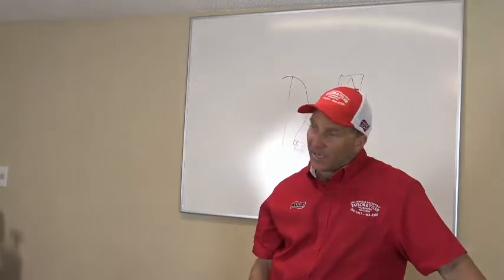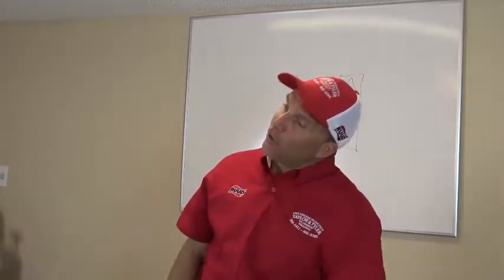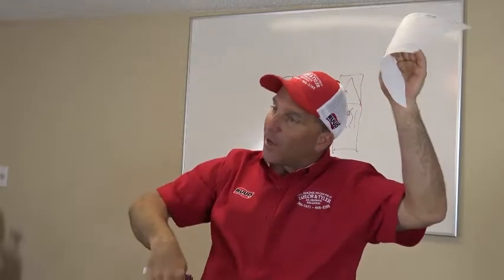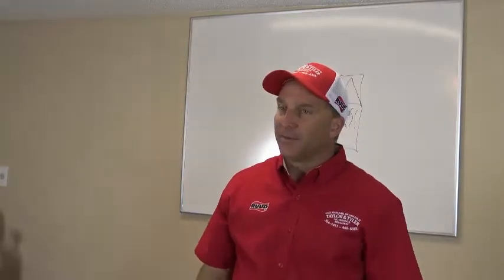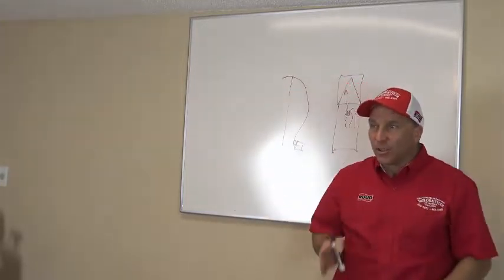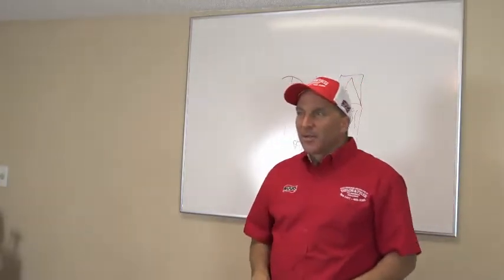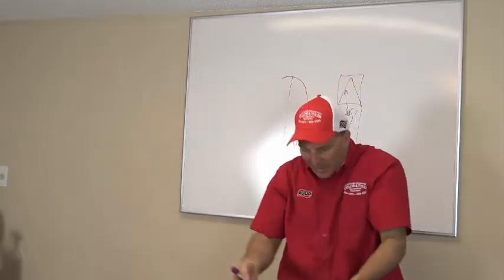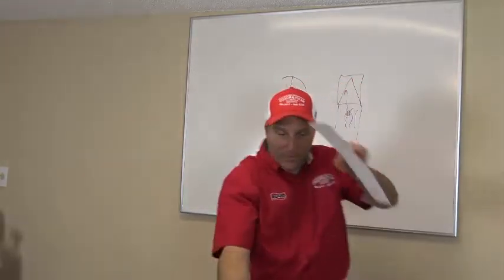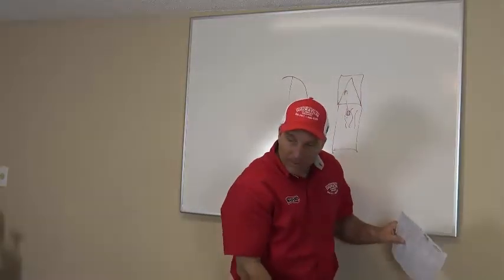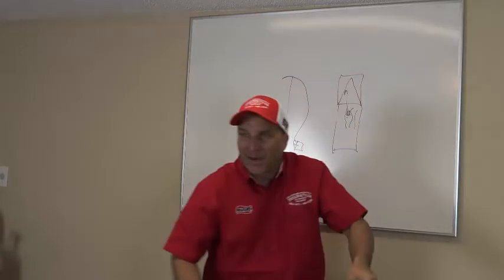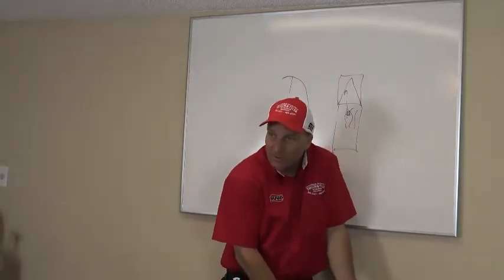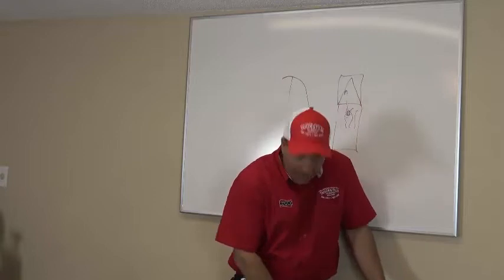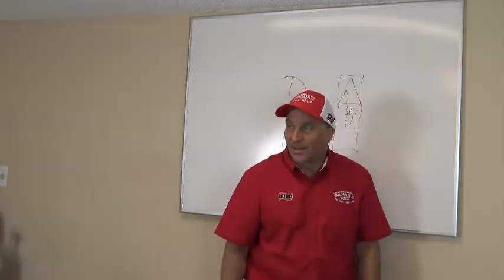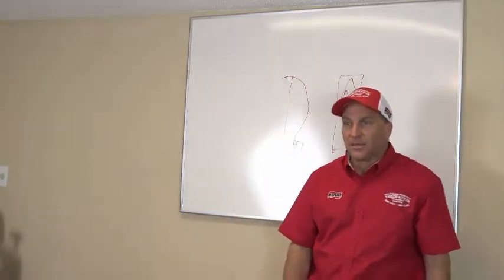Okay? If you stick your head inside there and you look up and you don't see the same size up top as you do below, it's restricted. Okay? Look at the transitions. Look to see how the transition's built. Sometimes you'll see a transition start here at the heater and it comes down like this. And then it comes from here and it goes like this and you go, wait, it was this big at the heater, and then it comes back down to this, and it's real small. Well, somebody just expects all that airflow to get through that little hole. Somebody needs to get some common sense. Can't get all that airflow through there, guys. Okay?